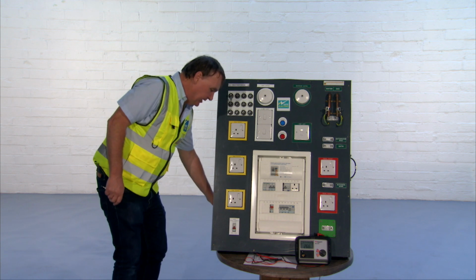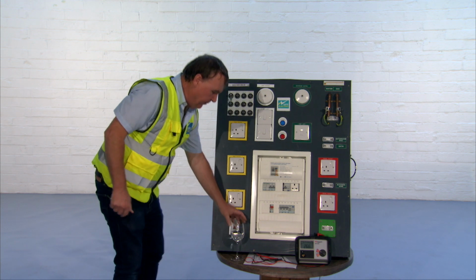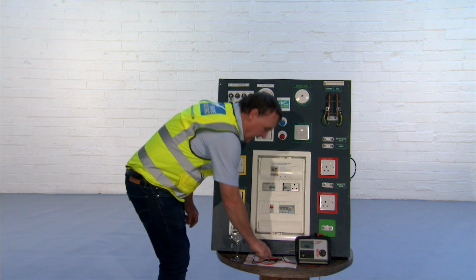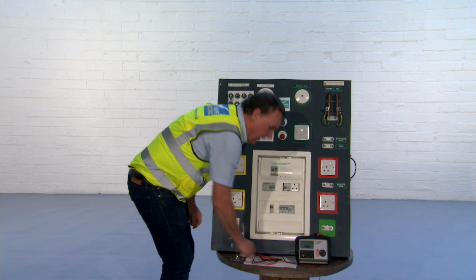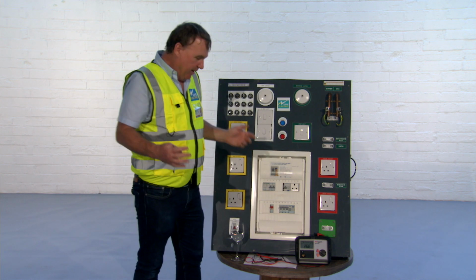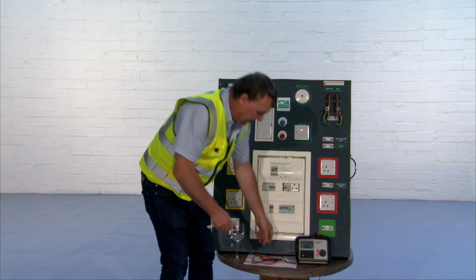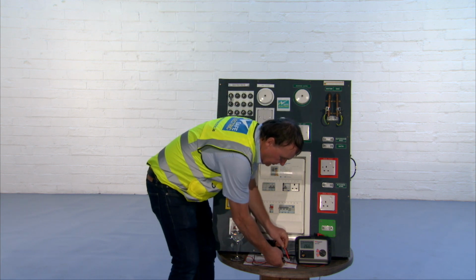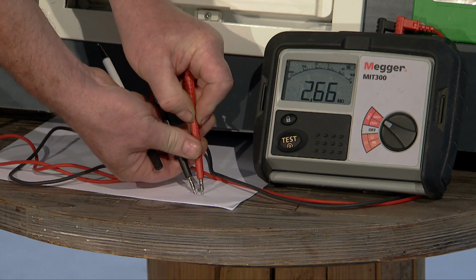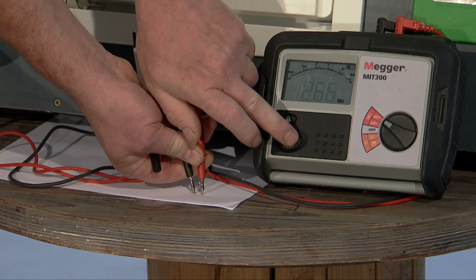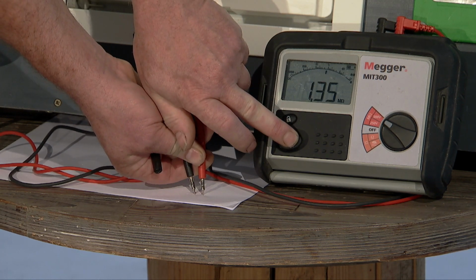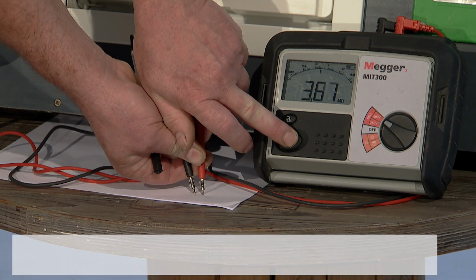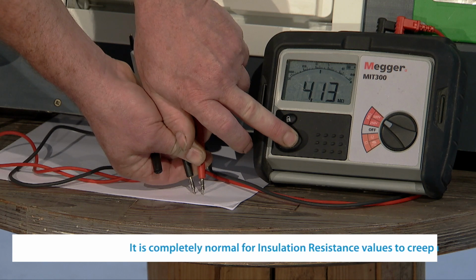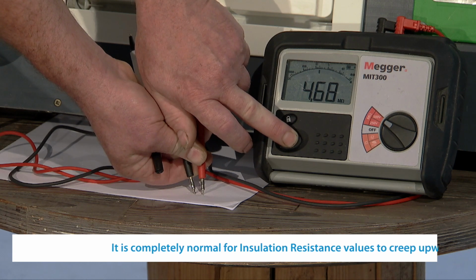But now we're going to change things. We're going to take some water, I'm going to wet my finger, and I'm going to apply a little bit of water across the two spots. And we're now going to repeat exactly the same test. I'm going to put the two probes back into the two spots, and our insulation resistance reading now, because the paper is wet, is 2.93, 3.4, 3.7. It's 4 mega ohms now and rising.